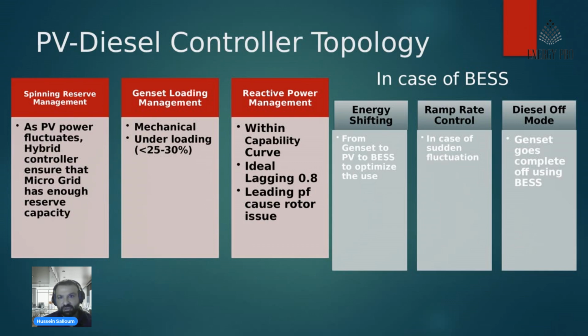So the PV diesel controller topology, without the battery, depends on 3 major controls that can be taken care of by the powerhouse controller. The first one is the spinning reserve management, where, because of the PV power fluctuation, the controller of the generator ensures that it keeps up to 30% of the generator running. And the other one will be the generator loading management, which will control its working between 30 to 90% of its capacity. It does not allow it to go below 30%, and it does not allow it to go above 90%. And it controls the input from the solar power accordingly.